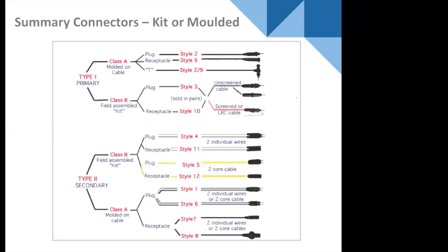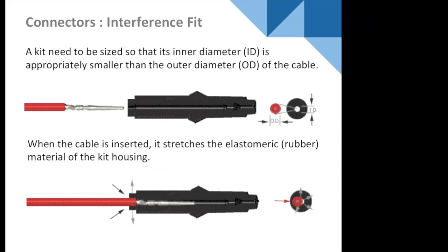Basically, when we're putting a connector onto a cable, this is using the male, showing the male connector rather than the female connector. And it's an interference fit because we want it to be watertight. So there's some criteria associated with how we make it watertight, and the instructions will come from the manufacturer of the connectors. And if we do not get it watertight, if we get this wrong, water will leak inside here, and it will short to earth, and then it will corrode, and it will blow open into an open circuit. And so we've got failure on both counts.